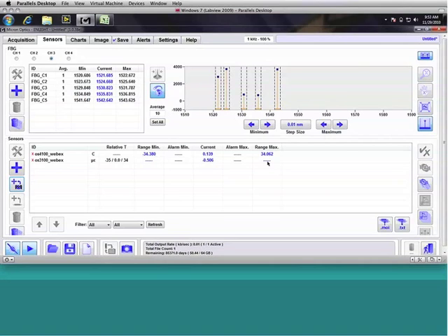So when we are creating our optical sensor networks, it's important to remember that our FBGs are going to see wavelength shifts from two factors. One is the measurement quantity for which the sensor has been designed: displacement, acceleration, strain, or whatever it might be.